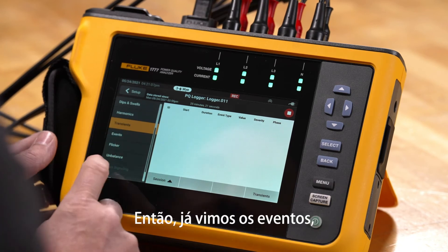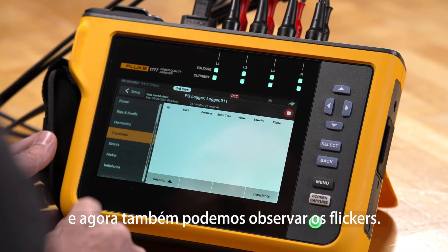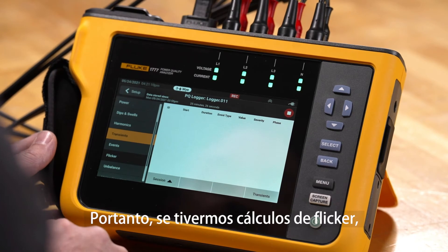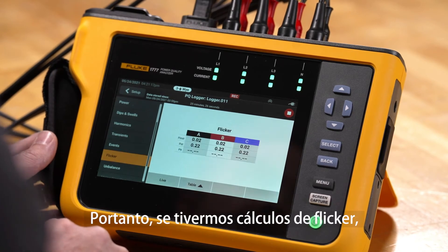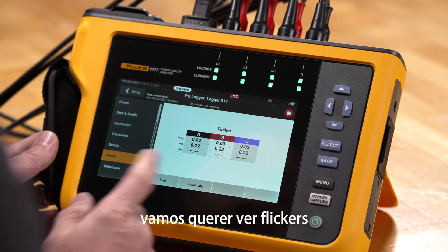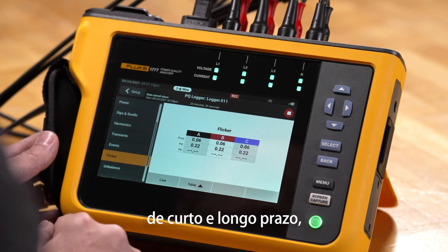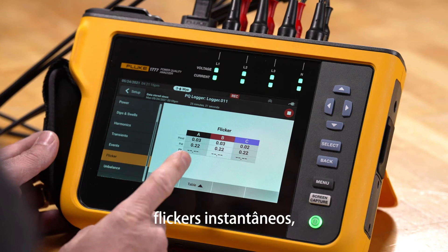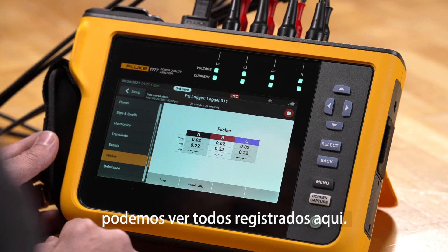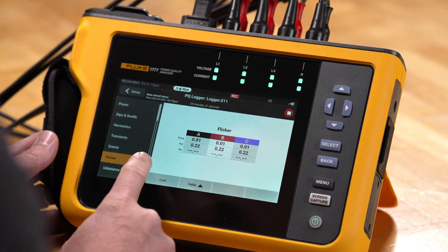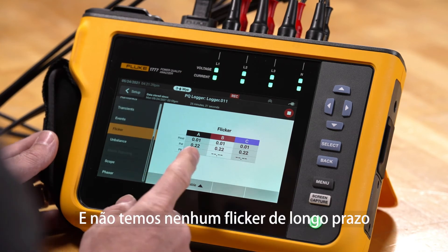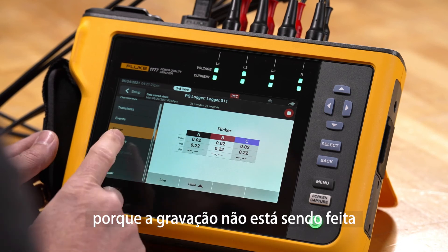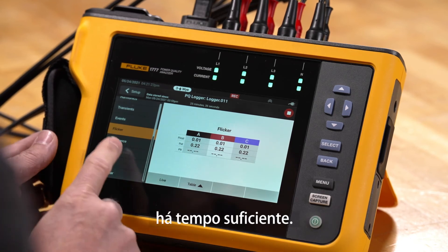We can also look at flicker. If we have flicker calculations we want to see — like short-term and long-term flicker, instantaneous flicker — we can see those logged here. We don't have any long-term flicker yet because the recording hasn't been going on long enough.